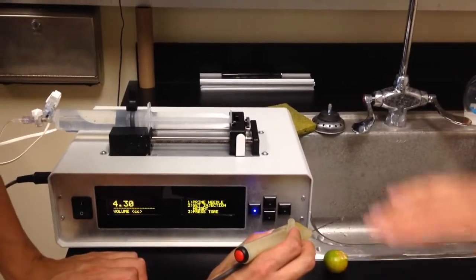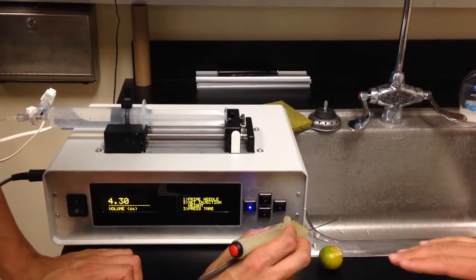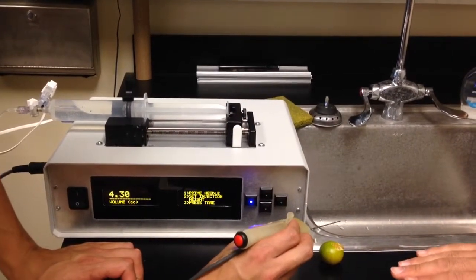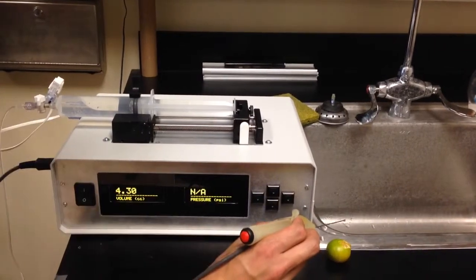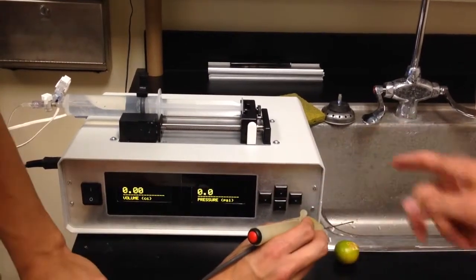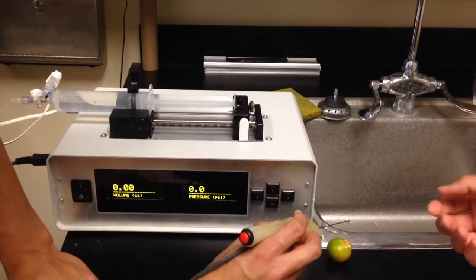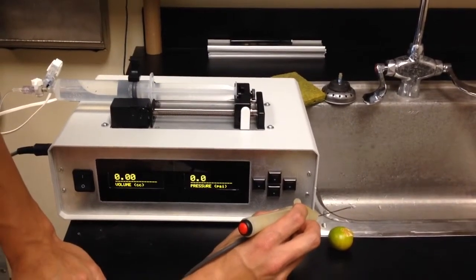Now, the next thing to do would be to set the injection height, number 2. This sets the reference height for the pressure readings, and the next thing would be to press the tare button, which zeroes the volume and sets the reference height. After that, you can inject.